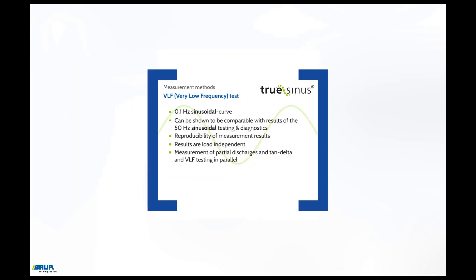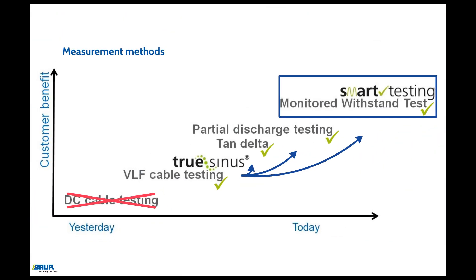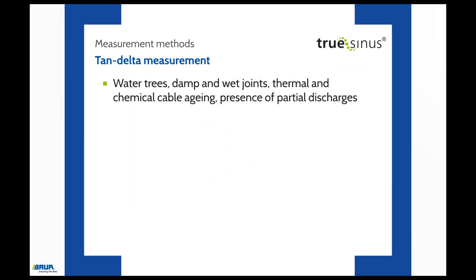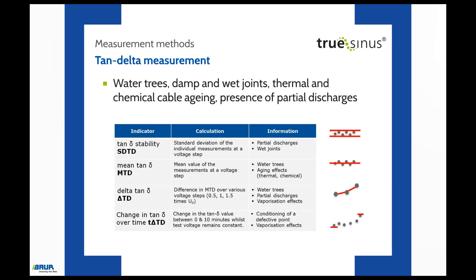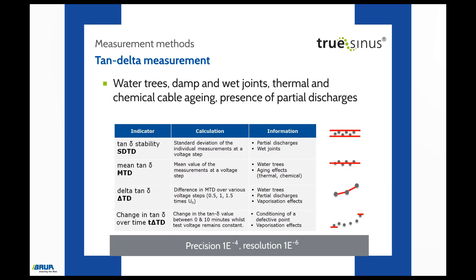The TAN-delta measurement provides information about water trees, damp and wet joints, and thermal and chemical cable aging. It also indicates the presence of partial discharges. Three parameters are needed for the TAN-delta measurement: mean TAN-delta, standard deviation, and delta TAN-delta. The standard deviation in particular provides a great deal of information. Prerequisites are a high TAN-delta precision of 1×10⁻⁴ and a high resolution of 1×10⁻⁶.